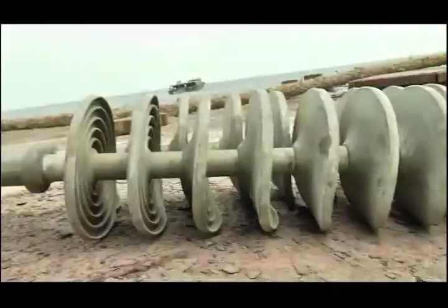Engineer Adegbola commended the MD and CEO of TCN, Usman Gur Mohammed, for the quick approval given for the replacement of the corroded glass insulators with silicone composite, which is anti-corrosive and better suited for the lagoon environment where the towers are located. Because of the corrosive nature of the environment, the insulators that carry the conductors get easily corroded, so there's a need for preventive replacement as and when due.